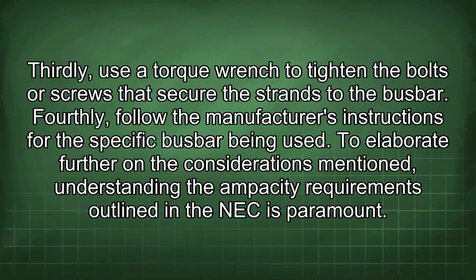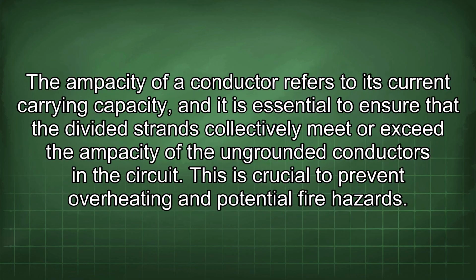To elaborate further on the considerations mentioned, understanding the ampacity requirements outlined in the NEC is paramount. The ampacity of a conductor refers to its current carrying capacity, and it is essential to ensure that the divided strands collectively meet or exceed the ampacity of the ungrounded conductors in the circuit. This is crucial to prevent overheating and potential fire hazards.